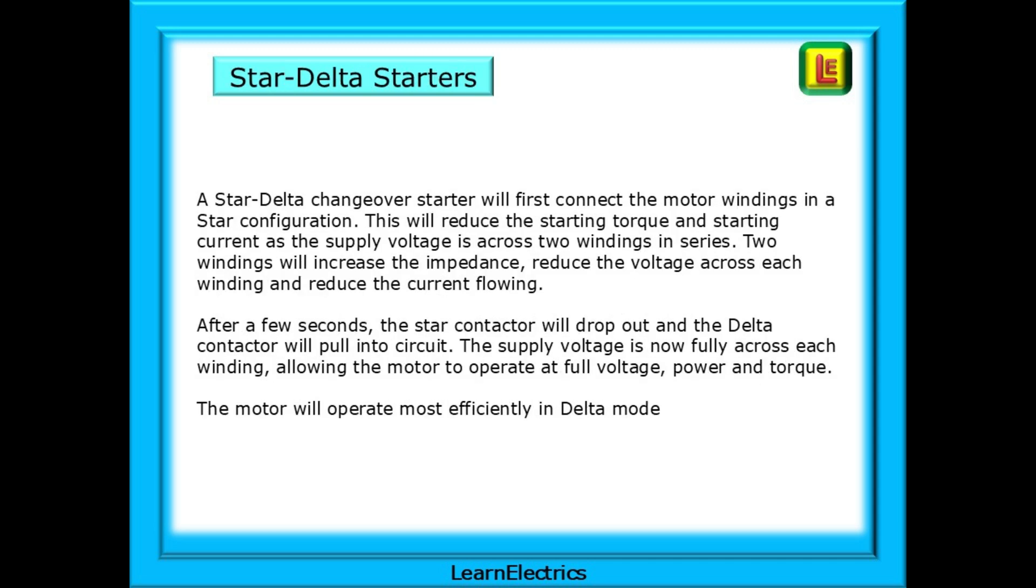A star delta starter will first connect the motor windings in a star configuration. This will reduce the starting torque and starting current as the supply voltage is across two windings in series. Two windings in series will increase the impedance, reduce the voltage across each winding, and reduce the current flowing. After a few seconds, the star contactor will drop out and the delta contactor will pull into circuit. The supply voltage is now fully across each winding, allowing the motor to operate at full voltage, power, and torque. The motor will operate most efficiently in this delta mode.